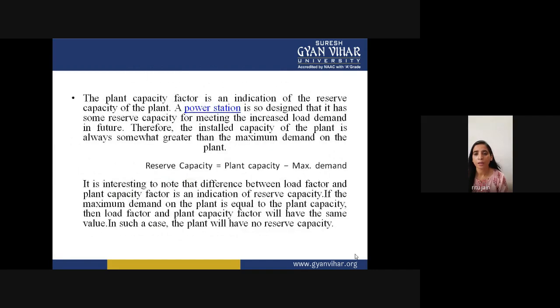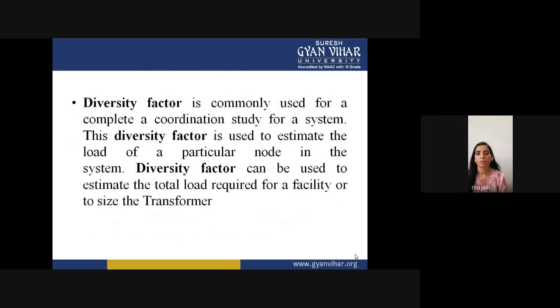If you are able to find out your diversity factor, for different users using maximum demand at different times, then you will be able to coordinate a study for a system. This diversity factor is used to estimate the load of a particular node in the system. So diversity factor can be used to estimate the total load required for a facility or to size the transformer.